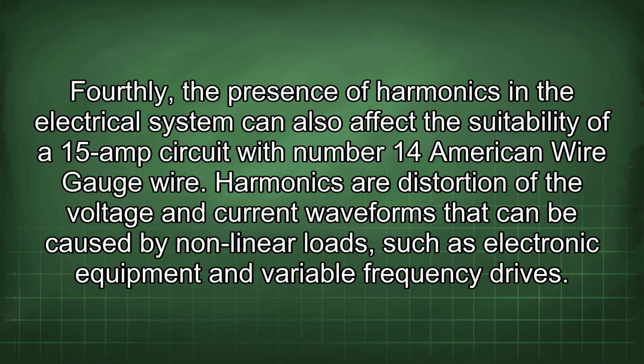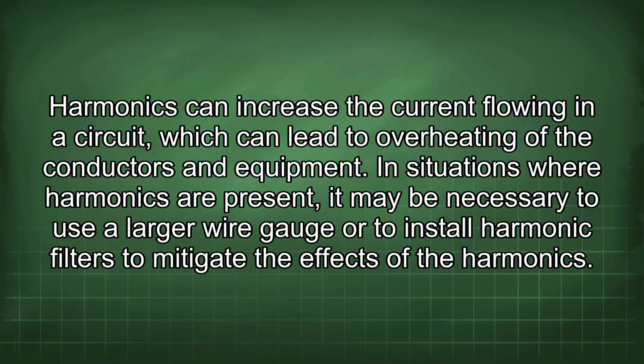Fourthly, the presence of harmonics in the electrical system can also affect the suitability of a 15 amp circuit with number 14 American wire gauge wire. Harmonics are distortions of the voltage and current waveforms that can be caused by nonlinear loads, such as electronic equipment and variable frequency drives. Harmonics can increase the current flowing in a circuit, which can lead to overheating of the conductors and equipment. In situations where harmonics are present, it may be necessary to use a larger wire gauge or to install harmonic filters to mitigate the effects of the harmonics.